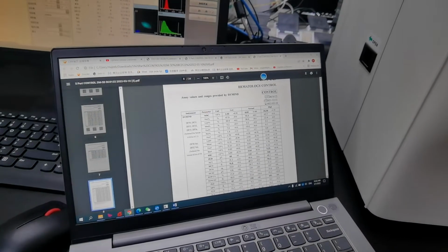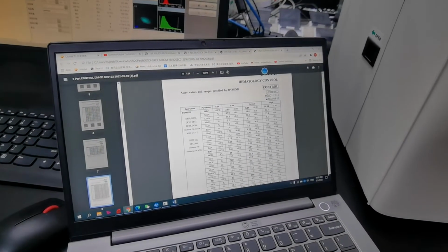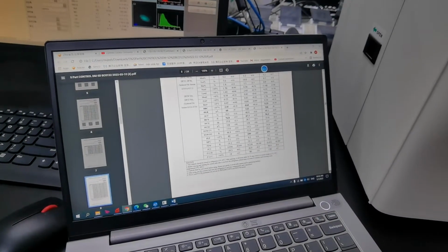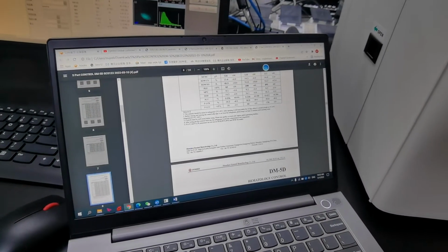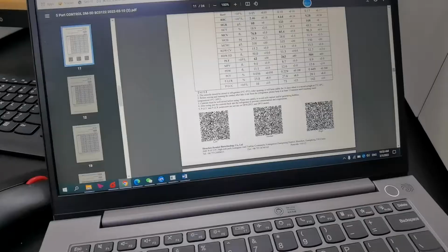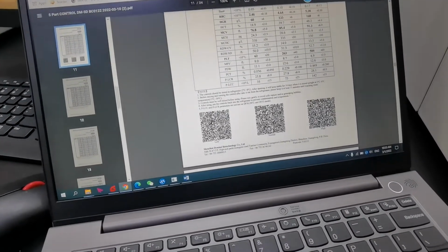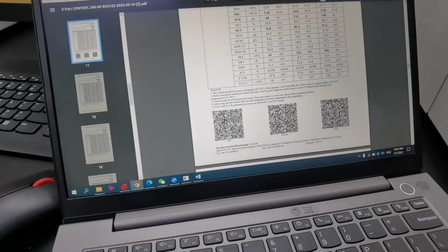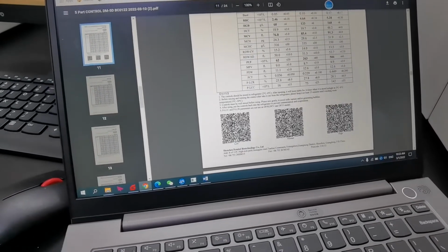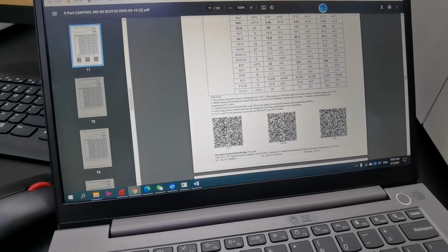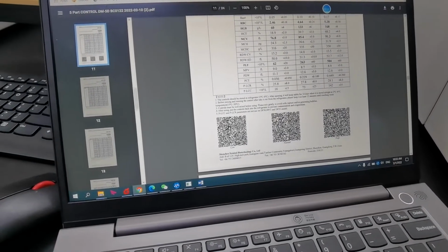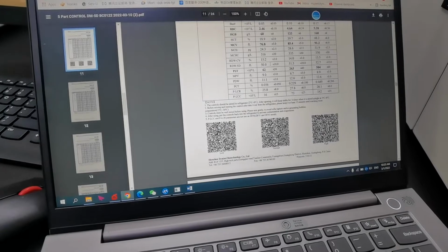These values. And there are two methods to input the target value in the system. One is manually. And this one, this is the QR code you can see. We have an external barcode device, you have to scan this value and automatically it will insert it into the analyzer, right? Now I'm gonna show you how to do it manually. These are the values, you will have this sheet, right?